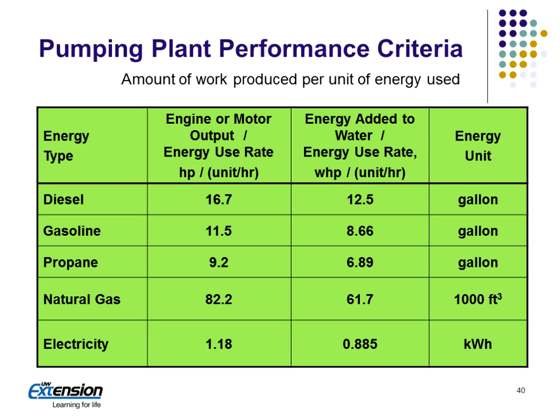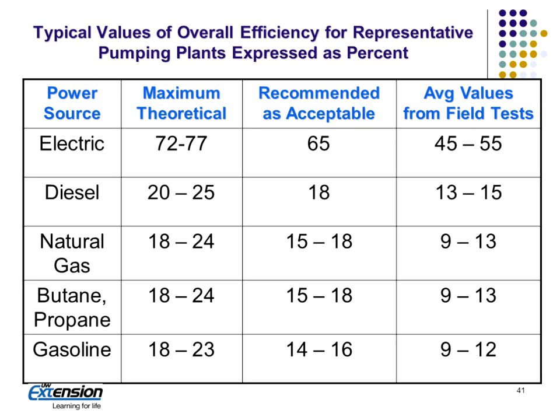So what is the pumping plant criteria? Basically, it depends on the type of fuel we're using for it. But this third column over here is the water horsepower. This is the amount of energy that we're actually adding to the water. And this is the amount of horsepower we'd need to generate from our engine, the output of the engine, to supply this amount of horsepower into the water horsepower. So it's going to depend on the type of fuel that's being used.